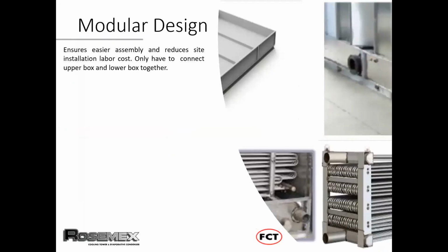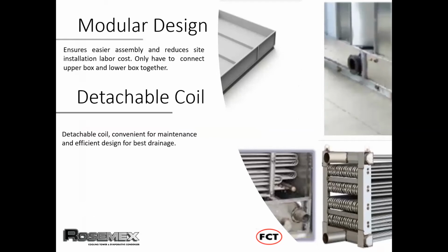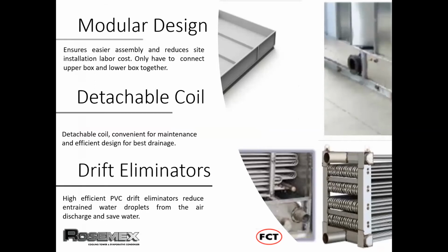Also, our design is modular, so it ensures easier assembly and reduces site installation labor cost, as you only have to connect the upper box and lower box together. We have a detachable coil, which is very convenient for maintenance and an efficient design for best drainage. For the drift eliminators, we use a high efficiency PVC drift eliminator to reduce entrained water droplets from the air discharge and save water.